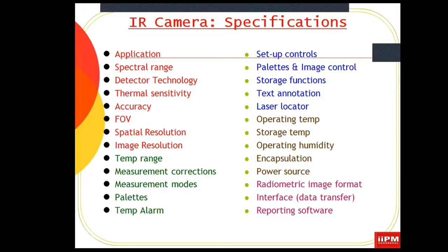It will take time, sir. Everything is available in the catalog. If you want to purchase, the most important thing in the thermography camera is that you have to set the emissivity. Emissivity is everything. For surface temperature, with different colors, if the emissivity setting is not accurate, the reading is wrong. Some cameras have an auto setting; in some cameras we manually set the emissivity for the actual surface color. Some surfaces like aluminum and mirror are reflective, shining or glazing surfaces, so emissivity setting is very important.